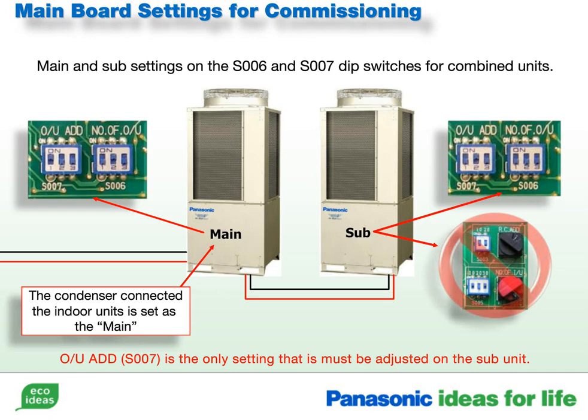On the main unit, you must configure the refrigerant circuit number, total number of indoor units, the total number of outdoor units and the outdoor unit address. The only setting on the sub-unit, or units, that must be configured, is the outdoor unit address. It is also labeled S007. When you are configuring a condenser as a sub-unit, it is controlled by the main outdoor unit.